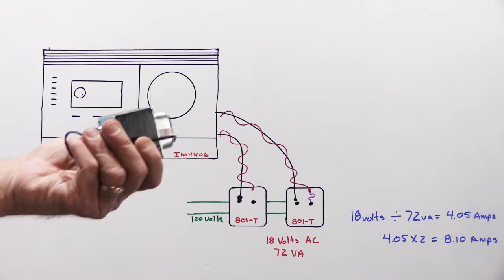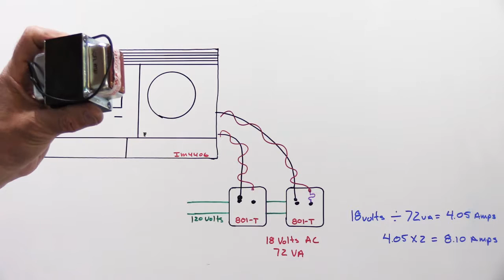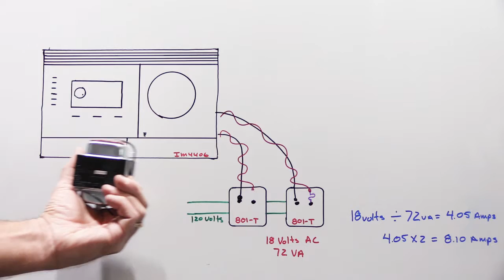I know someone in our local area, another company, not a NuTone service center, who started doing a service call for a homeowner on a 4406. She had bad transformers, and he bought two new ones from me. This was probably five or six years ago when these were more readily available. He went back out on the second service call, installed the two new transformers, hooked up the power lines from the master station to it, turned on the circuit breaker, and immediately blew up the two new transformers because the failure was in the master station.